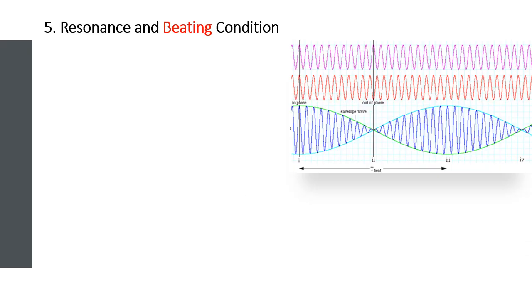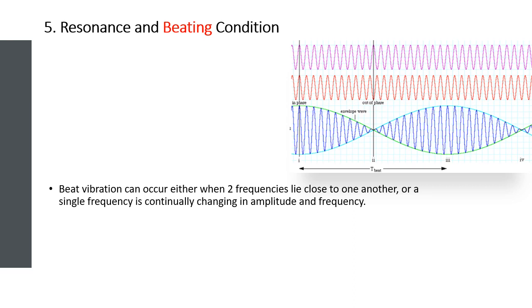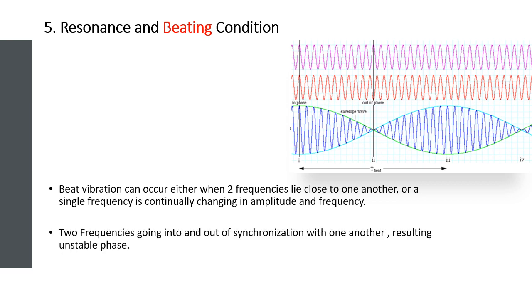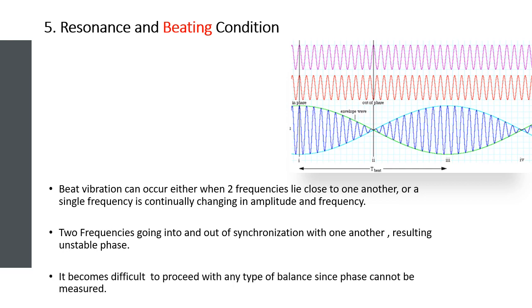The beating condition occurs when either two frequencies lie close to one another or a single frequency is continuously changing in amplitude and frequency. This commonly happens with machines sharing a common base or in close proximity and operating at similar speeds. The two frequencies go in and out of synchronization — when in phase, vibrations amplify; when out of phase, vibrations diminish. This results in unstable phase readings, making the balancing program very difficult.